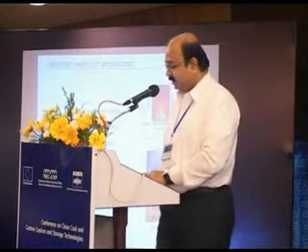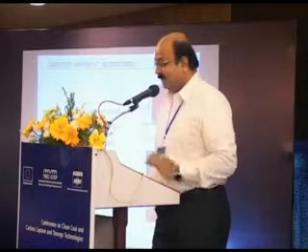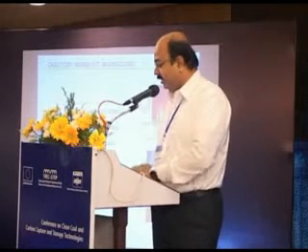And then the burner panels, it's a low NOx burner with a tiled refractory throat. You can see how things were before on the left hand side, and on the right hand side you can see how things are after. This is not this boiler, this is some other boiler which had a similar modification done. You will see that the slagging is not there. That's because of the refractory tiling that we do, the cooling would not happen, and the heat is given back to the flame, and then it won't settle. The cold portions around, because of the tubes which go around, will now be covered with refractory tiling. So that will give the heat back to the ash, and then it won't form any slag around the burner.